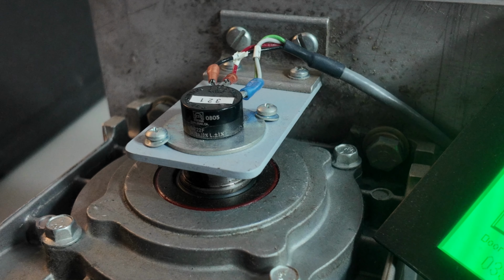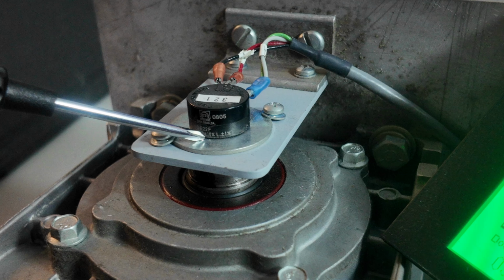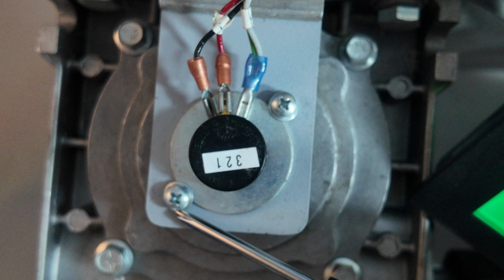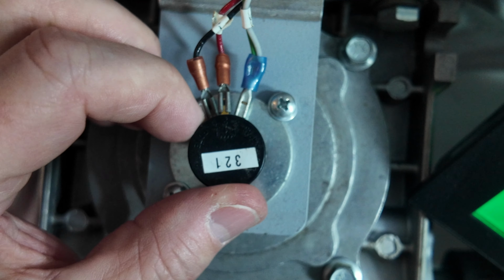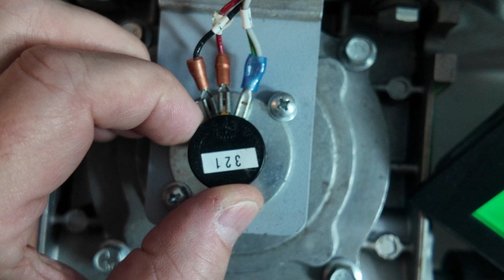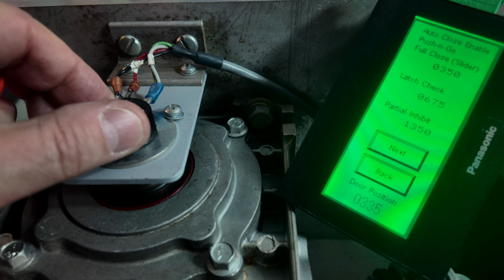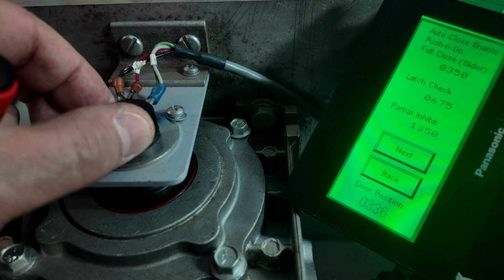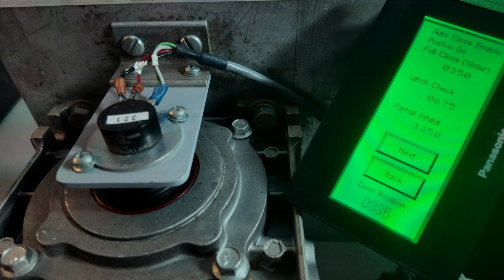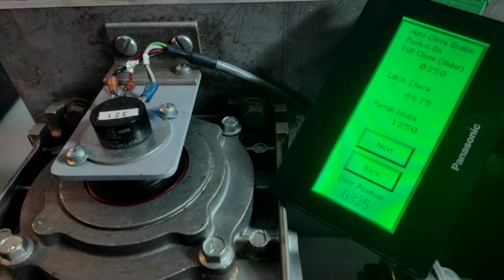Lastly, there's a small plastic pin molded into the bottom of the transducer. This pin sits in a hole in the washer that it's mounted to. The screws are easy to check. The pin can be verified by giving the transducer a gentle twist, and you should see very little to no door position change. Alternatively, you'll need to remove the transducer and washer from the bracket, and then the transducer from the washer to see if the pin is broken.